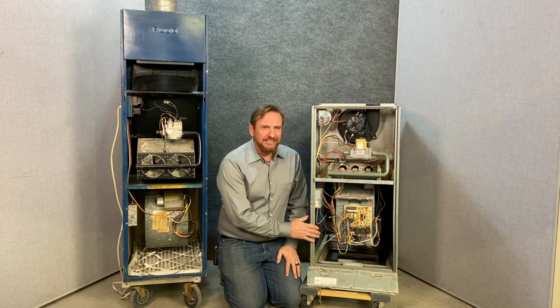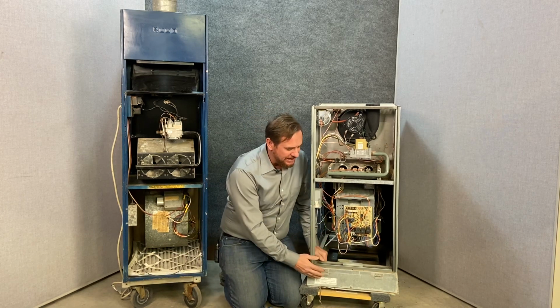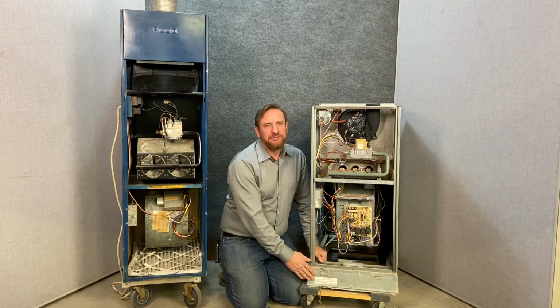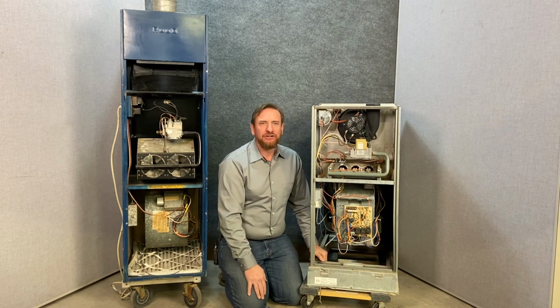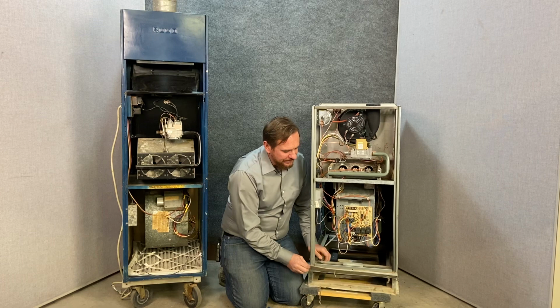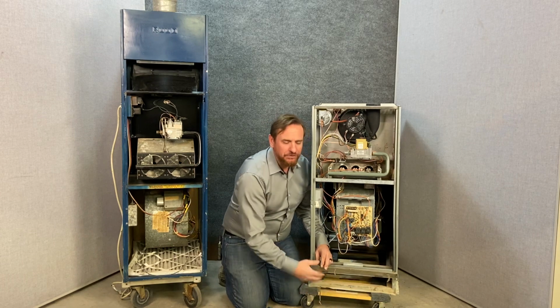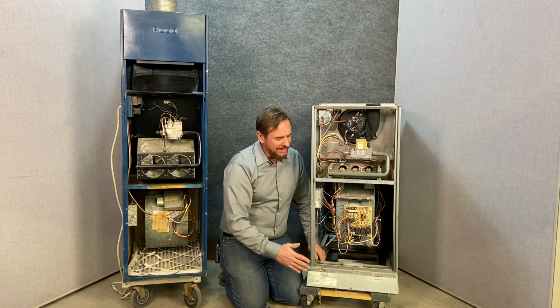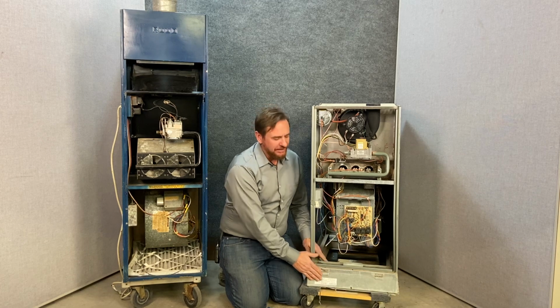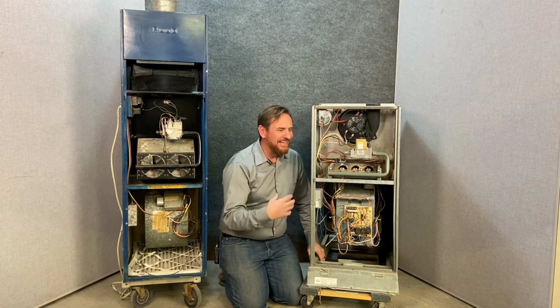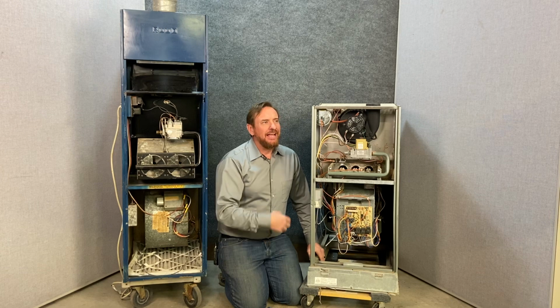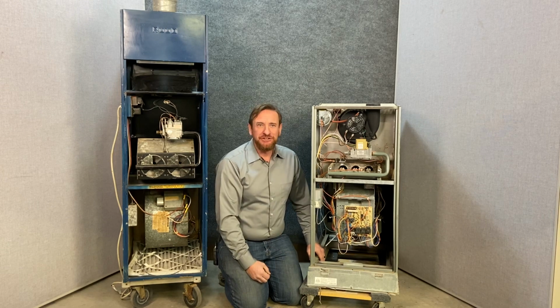On this furnace, it's a little bit more modern, because in addition, somebody has added an external filter base. These filter bases are great because you can open this and slide the filter in and out without taking the door off. So I've never installed a furnace without installing one of these external filter bases, because it's so much easier for that customer. It's hard enough getting your customer to change filters anyways.